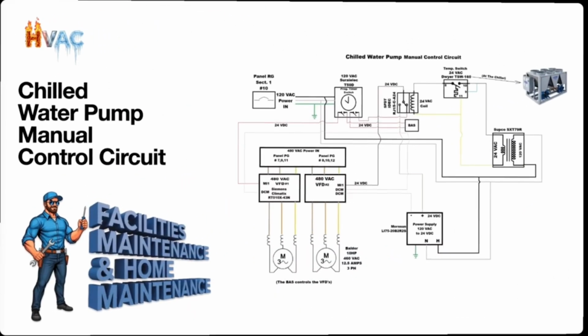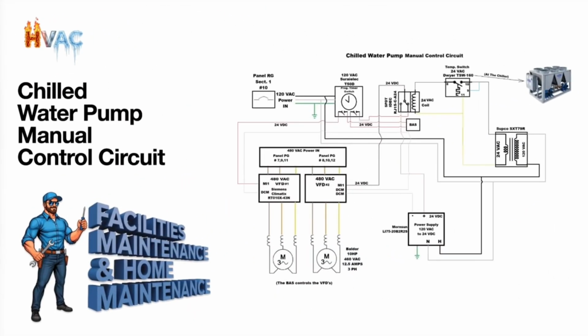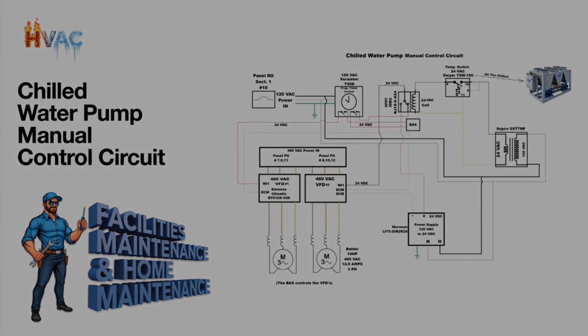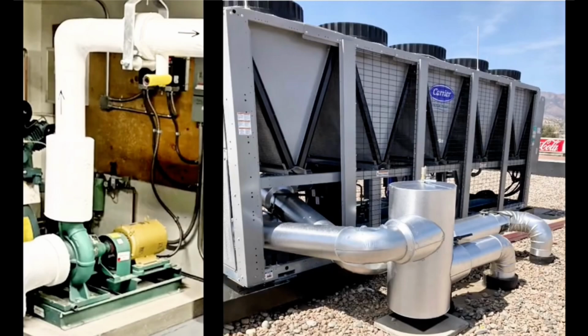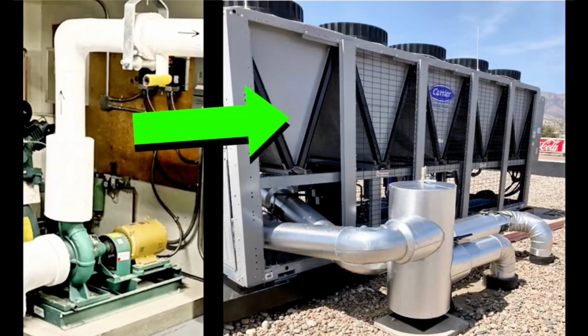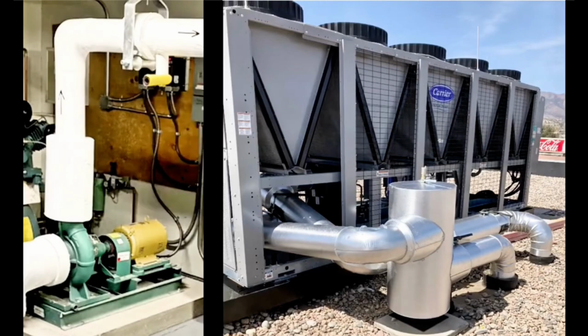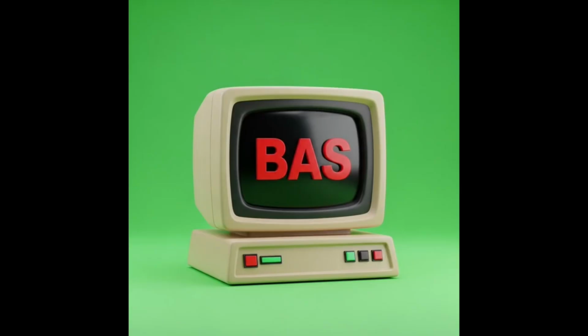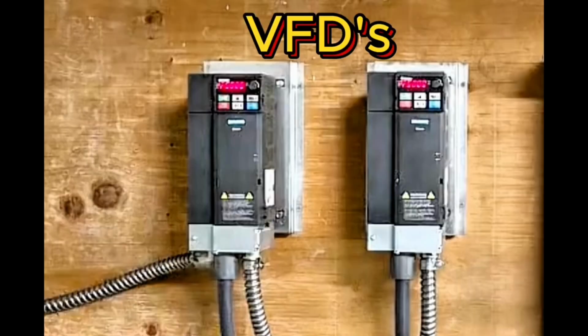Okay, today we're talking about a chilled water pump manual control circuit. To give you some context, in this commercial office building, we installed a new chiller, new water pumps, and a new BAS, building automation system, and new VFDs, variable frequency drives.